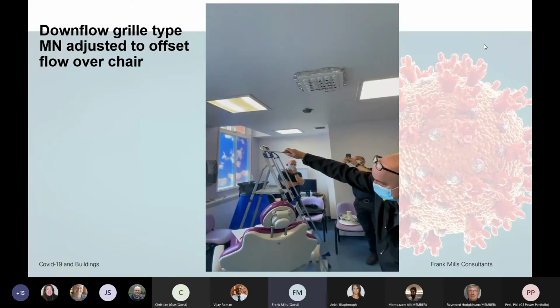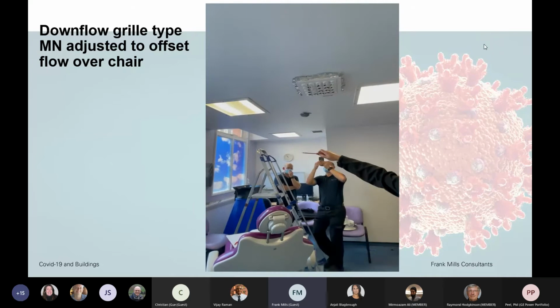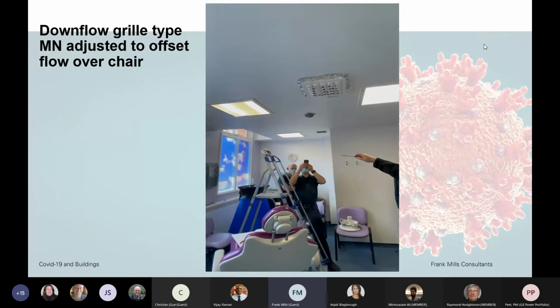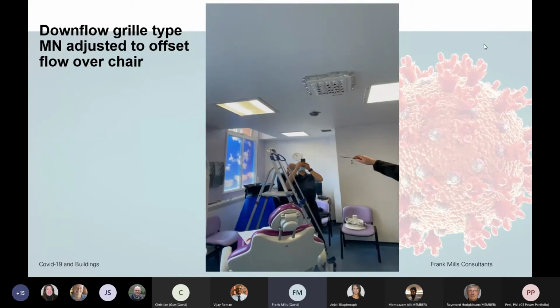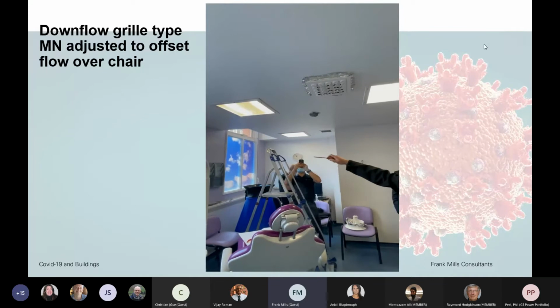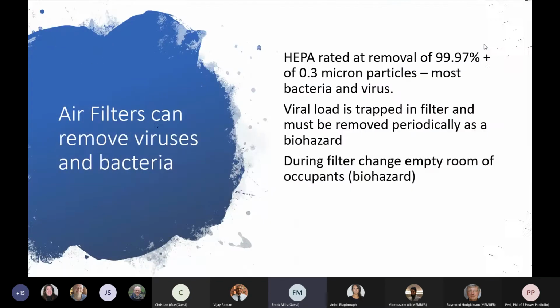And then over at the back of the unit there, we have a mobile UV air cleaner. So this is a hospital application with clean air coming from the ceiling. Unfortunately, what we've found in this situation is the air change rate was only 5. We should have 10, but we have 5. And you will find this, as engineers, when you go out, that the air change rates don't comply with the standard anyway.